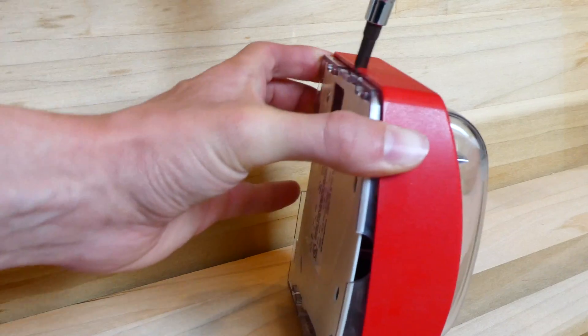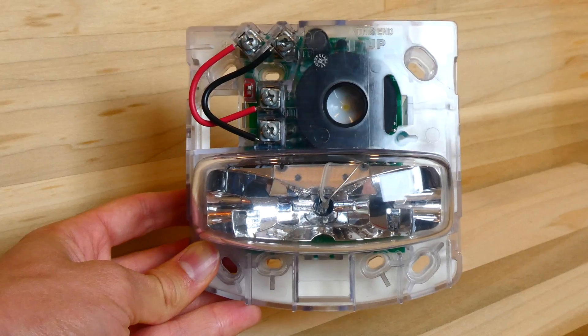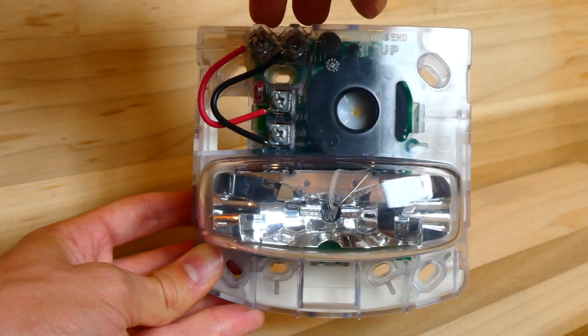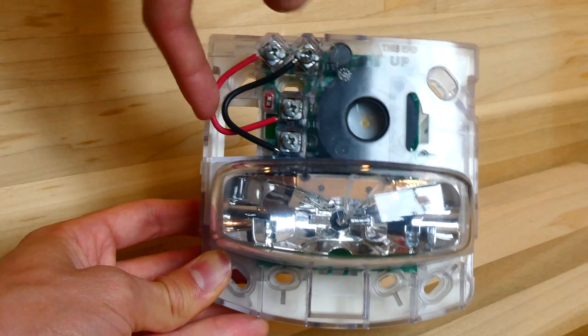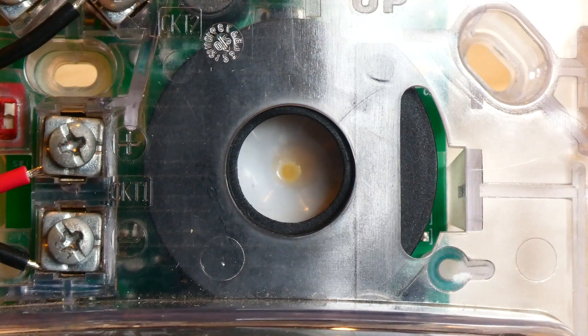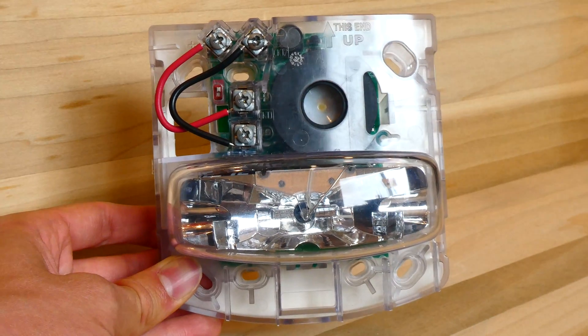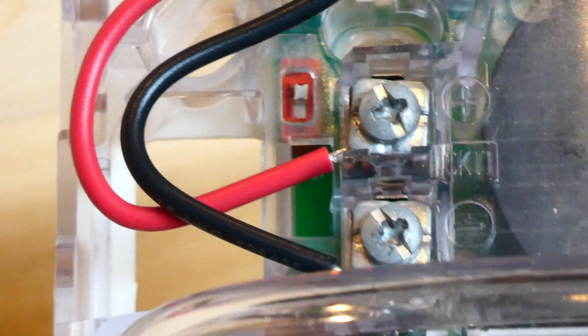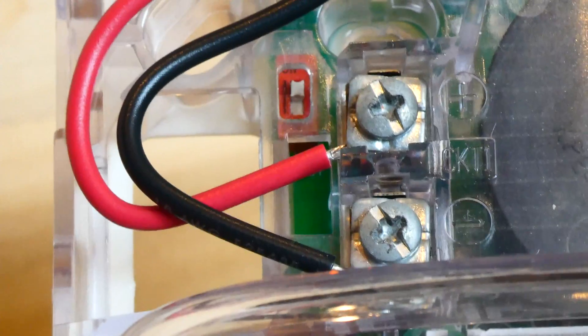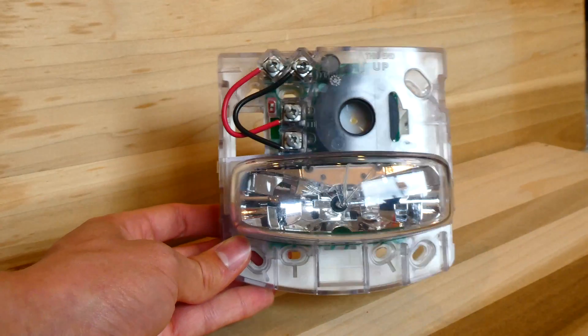You can use a screwdriver on the sides to pop off the plastic cover, and when you do that, you get to see the inside. The free run version that I have here is a 4-wire TruAlert. Most of the SmartSync TruAlerts are just going to be 2-wire. So as you can see, you have 2 wires powering the horn and 2 wires powering the strobe. And if you want to use 2-wire operation, you just put in jumpers, like I did here. This is the horn of the alarm. Simplex made a couple different mounting options for the back box, and it's most commonly used on a double gang or a single gang back box. Right next to the terminal, you can see there is a little red switch there, and that switch can actually change the TruAlert into a SmartSync or a free run TruAlert. So with this model, you have that option of changing it between the different styles, which is very nice for collectors.